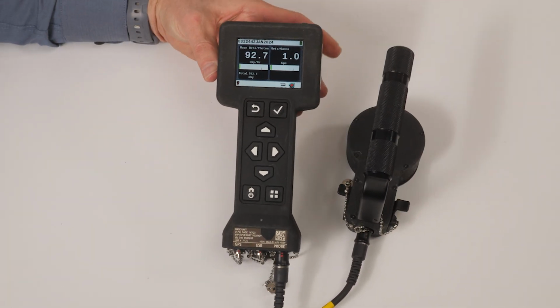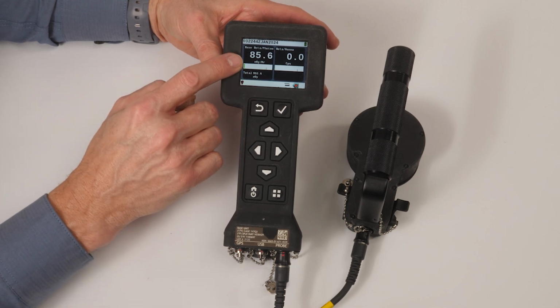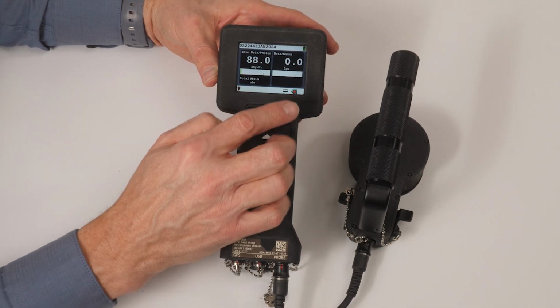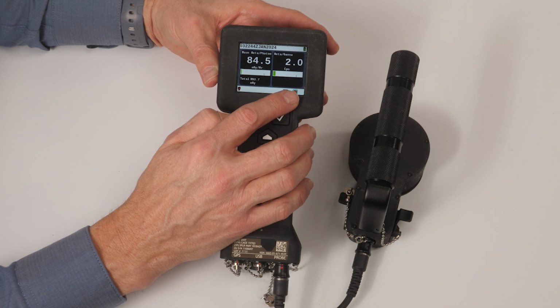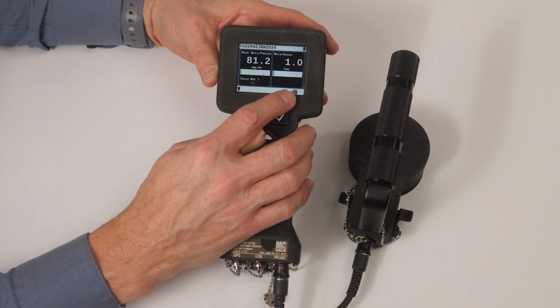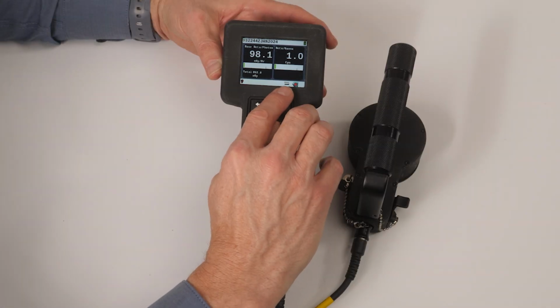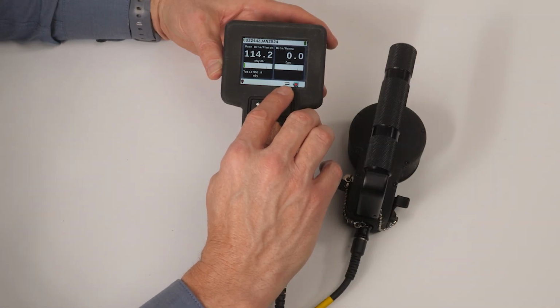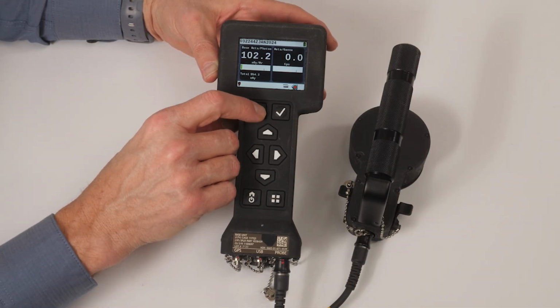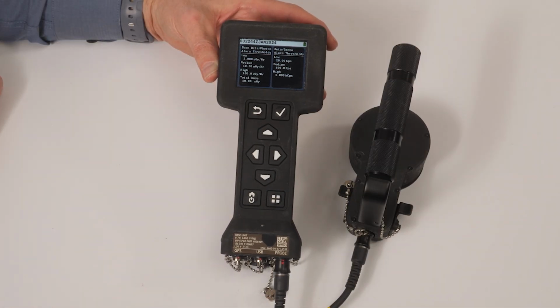Then check the base unit home screen to verify it displays the base beta photon radiation reading for the base unit, the beta gamma radiation reading panel for the small area beta gamma or SABG probe, and then verify that the SABG probe icon displays on the bottom of the screen. Verify that the correct units of measurement are displayed in accordance with your survey or mission requirements. While on the home screen, press the back key to display the alarm thresholds. This screen will only display for 5 seconds, then will return to the home screen.